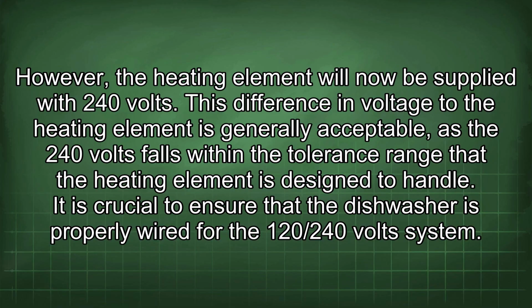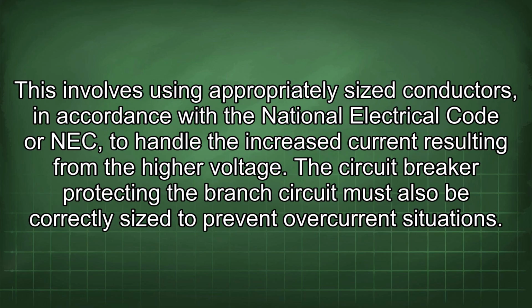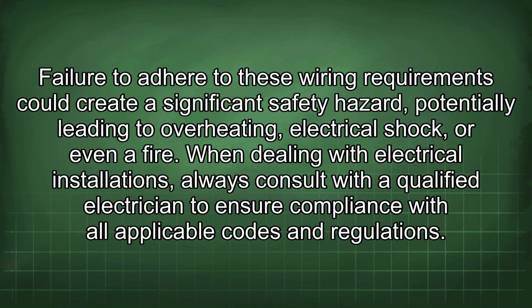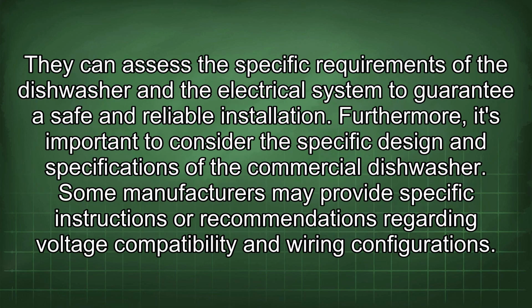It is crucial to ensure that the dishwasher is properly wired for the 120/240 volt system. This involves using appropriately sized conductors, in accordance with the National Electrical Code or NEC, to handle the increased current resulting from the higher voltage. The circuit breaker protecting the branch circuit must also be correctly sized to prevent overcurrent situations. Failure to adhere to these wiring requirements could create a significant safety hazard, potentially leading to overheating, electrical shock, or even a fire. When dealing with electrical installations, always consult with a qualified electrician to ensure compliance with all applicable codes and regulations.